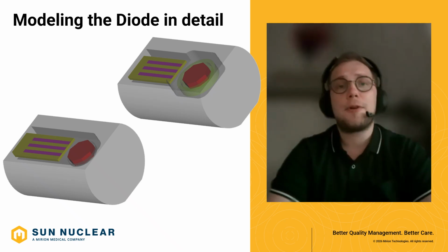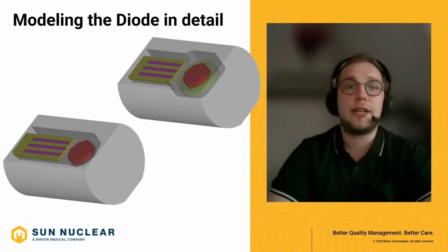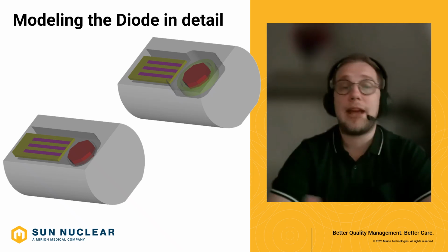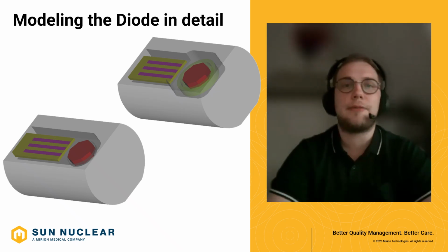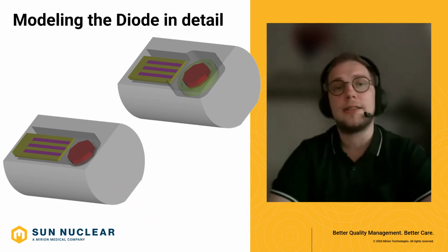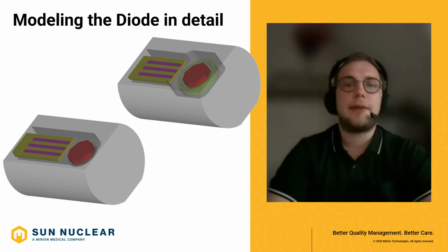The authors therefore created detailed Monte Carlo models of both diodes. As shown here, they contain the same silicon chip, while SunSILICON P includes an additional shielding layer around the active volume. Then the LINAC heads were completely simulated by EGSnrc, and the dose was stored in water and inside each detector model to calculate correction factors for field sizes from 0.6 to 40 centimeters. The simulated responses were then compared directly with measurements, and the final comparison validates the models used in the study.